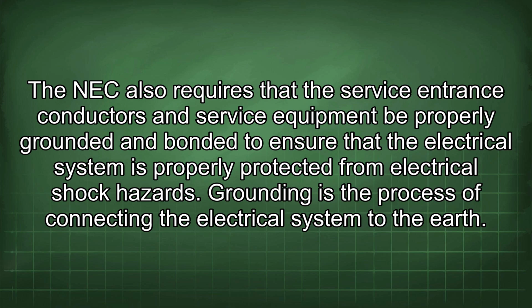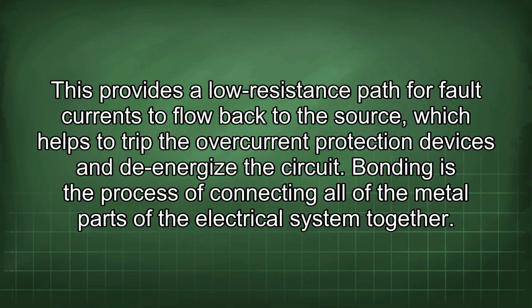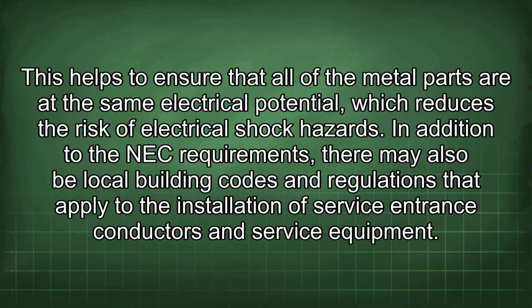Grounding is the process of connecting the electrical system to the earth. This provides a low-resistance path for fault currents to flow back to the source, which helps to trip the overcurrent protection devices and to de-energize the circuit. Bonding is the process of connecting all of the metal parts of the electrical system together. This helps to ensure that all of the metal parts are at the same electrical potential, which reduces the risk of electrical shock hazards.